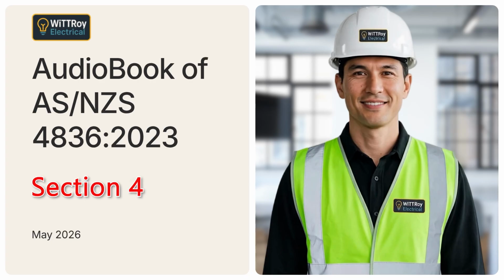Clause 4.3.7. Batteries and DC supplies. Clause 4.3.7 explains hazards from batteries and DC supplies. DC means direct current. Batteries and DC supplies can create several hazards. These include arc flash, electric shock, toxic fumes, chemical hazards, mechanical failure, and fire. Before working on or near batteries, DC supplies, or electrical equipment that contains them, a risk assessment must be carried out. Suitable precautions must then be put in place. These may include following the manufacturer's instructions, using insulated tools, and using PPE suitable for the available incident energy.